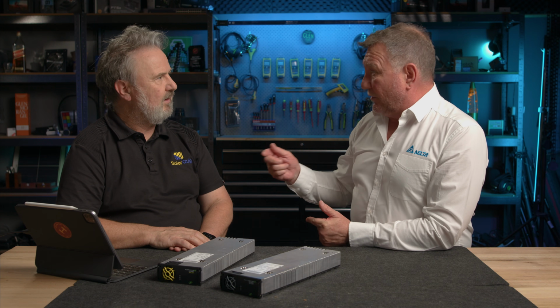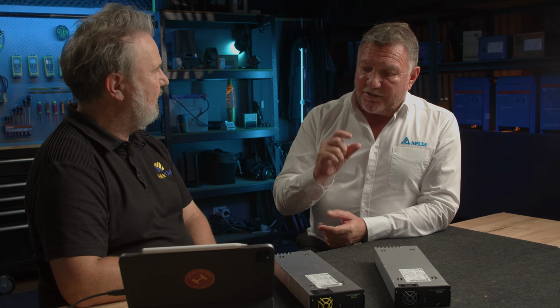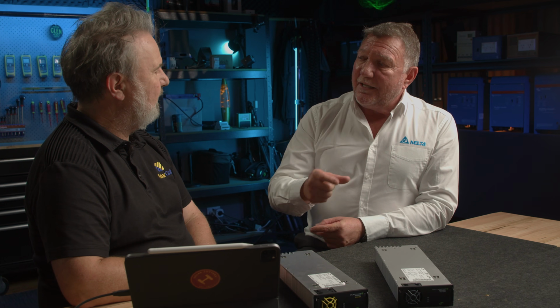We use another third-party product that connects to the grid to allow that. But that smart power functionality is actually built into the controller, and for a small license fee we'll turn it on - so you can offer services to the grid. Earlier when I asked if it can be connected to the grid, the answer was that it's not grid interactive without a third-party product, but it can be connected as a charging device, meaning it can absorb excess energy from the grid by charging batteries and be paid for it.